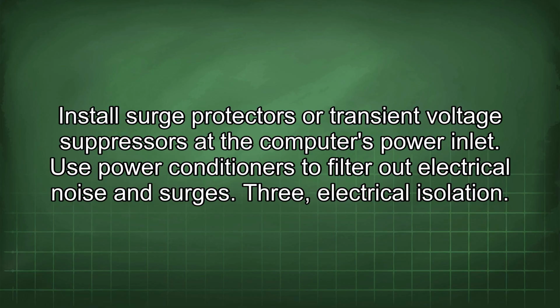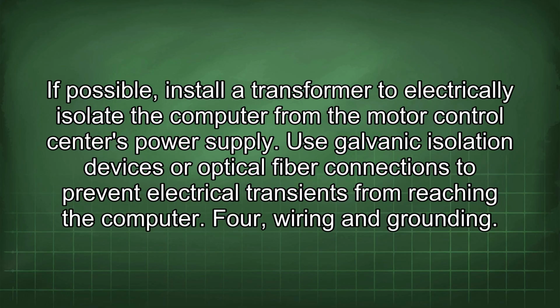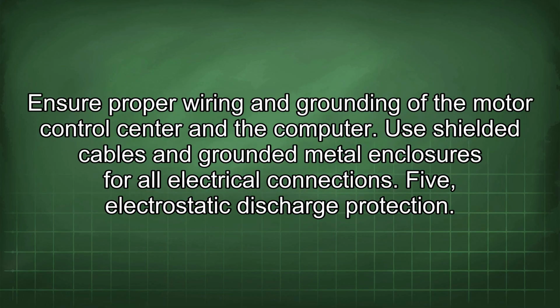3. Electrical isolation. If possible, install a transformer to electrically isolate the computer from the motor control center's power supply. Use galvanic isolation devices or optical fiber connections to prevent electrical transients from reaching the computer. 4. Wiring and grounding. Ensure proper wiring and grounding of the motor control center and the computer. Use shielded cables and grounded metal enclosures for all electrical connections.